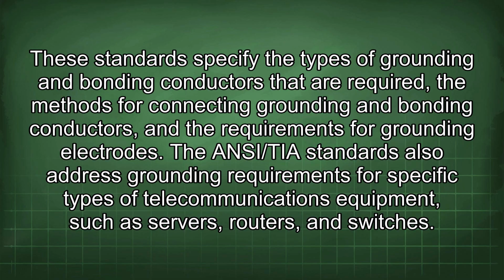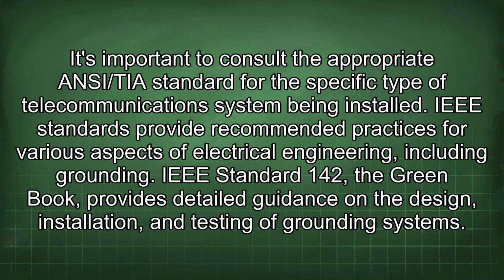These standards specify the types of grounding and bonding conductors that are required, the methods for connecting grounding and bonding conductors, and the requirements for grounding electrodes. The ANSI/TIA standards also address grounding requirements for specific types of telecommunications equipment, such as servers, routers, and switches. It's important to consult the appropriate ANSI/TIA standard for the specific type of telecommunications system being installed.